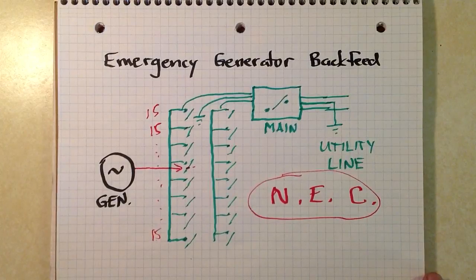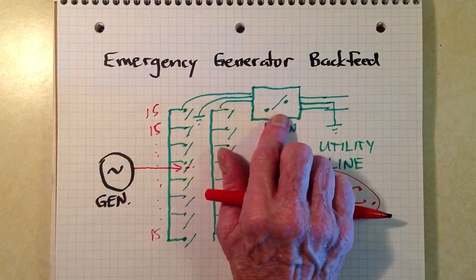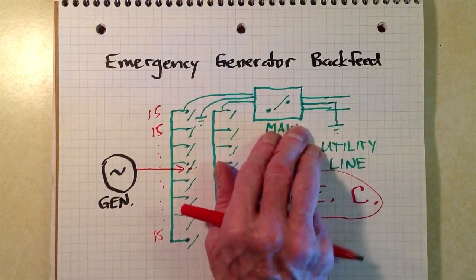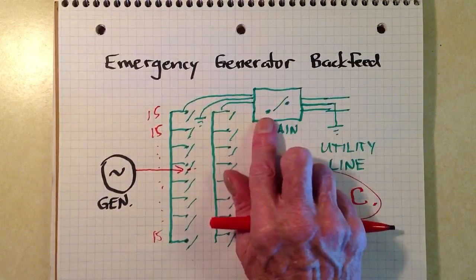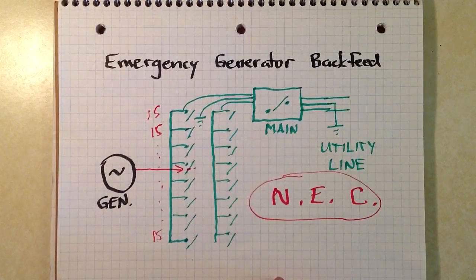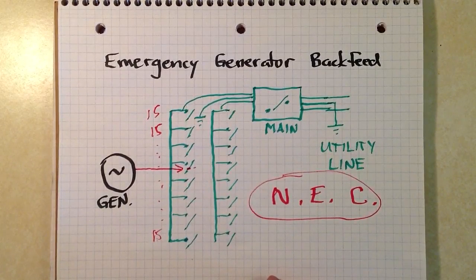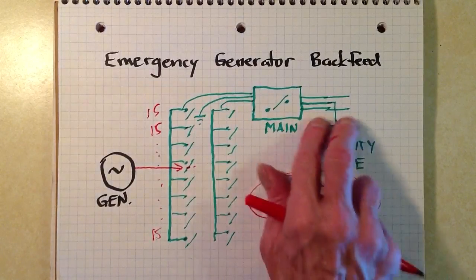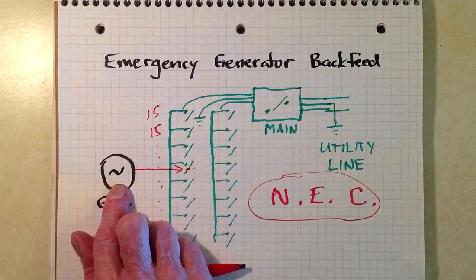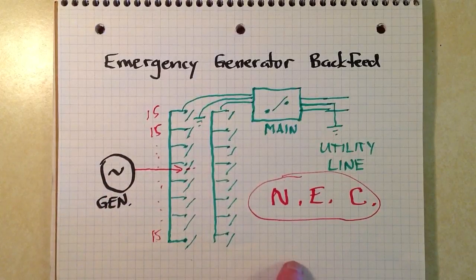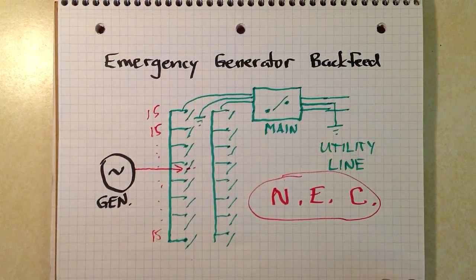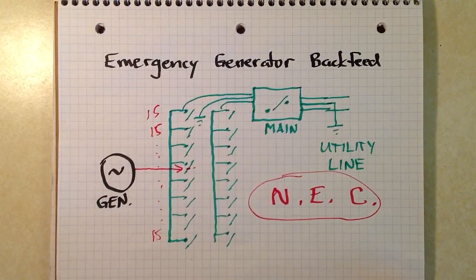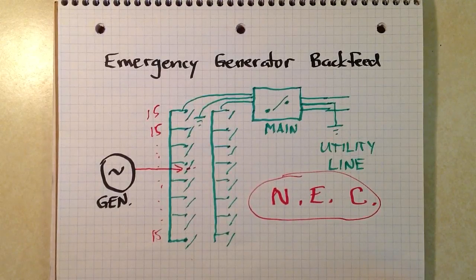Moreover, should you happen to forget about turning the generator off and disconnecting it before you turn that main breaker back on, when the utility power comes back on? If you switch that main on, just happen to forget to switch it on, while that generator is still connected and running, then the utility current is going to buck the generator current. More than likely, it'll blow the fuse in the generator. But it could also produce more serious side effects, which would wake you up in a hurry.